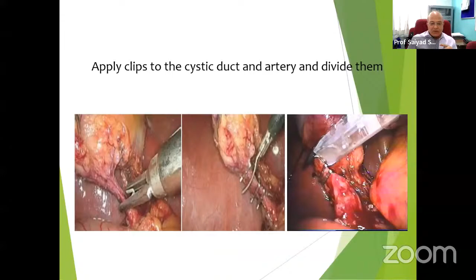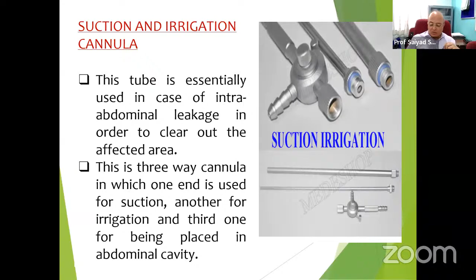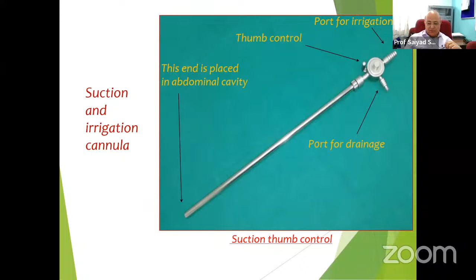And a suction and irrigation cannula. This tube is essentially used in case of intra-abdominal leakage in order to clear out the affected area. This is a 3-way cannula in which one end is used for suction, another for irrigation, and the third one is placed in the abdominal cavity as shown in this picture. There is a different port for drainage, one port for irrigation, and another is a tip in the abdominal cavity, with thumb control. You have the suction and irrigation with the help of thumb control. 5 mm and 10 mm according to your size.